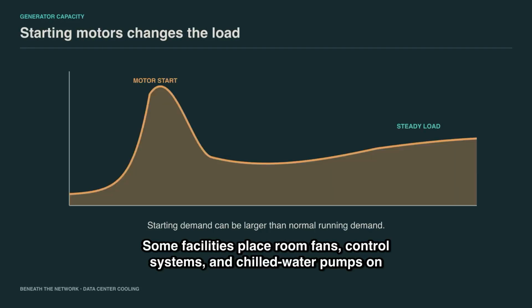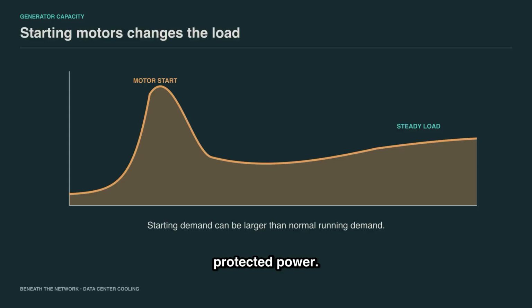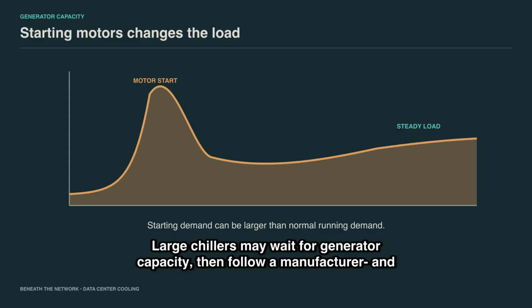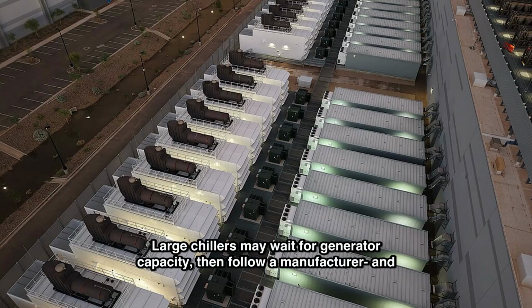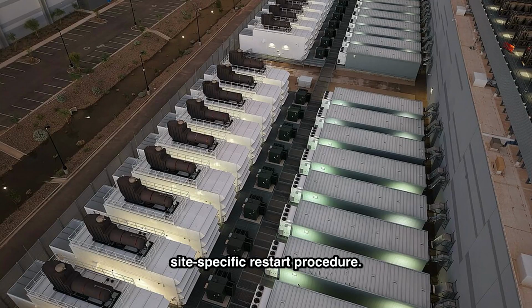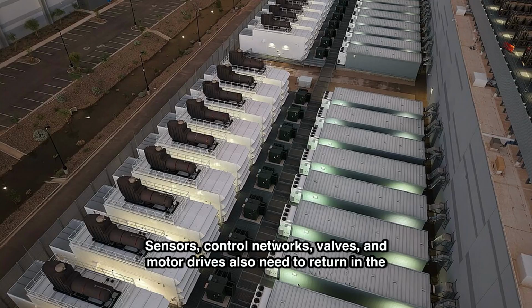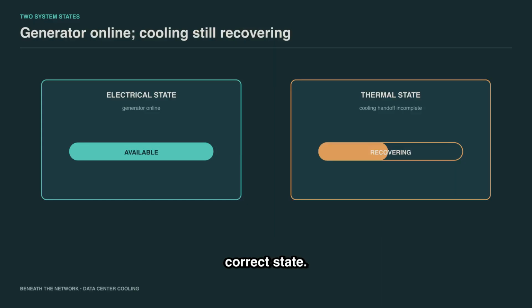Some facilities place room fans, control systems, and chilled water pumps on protected power. Large chillers may wait for generator capacity, then follow a manufacturer and site-specific restart procedure. Sensors, control networks, valves, and motor drives also need to return in the correct state.